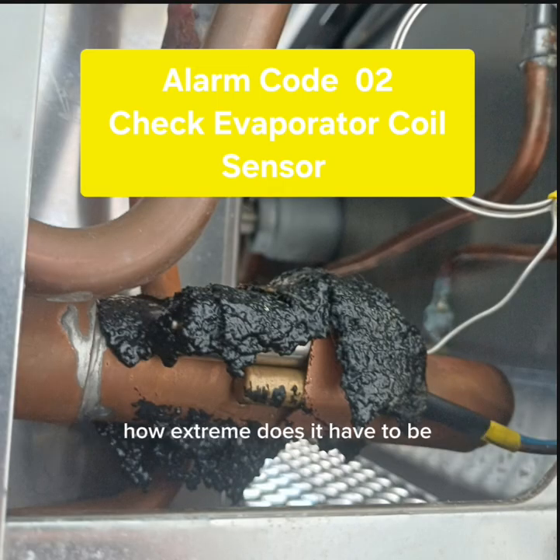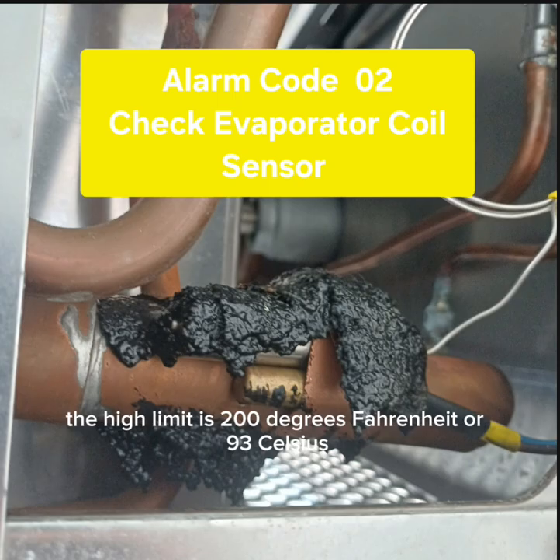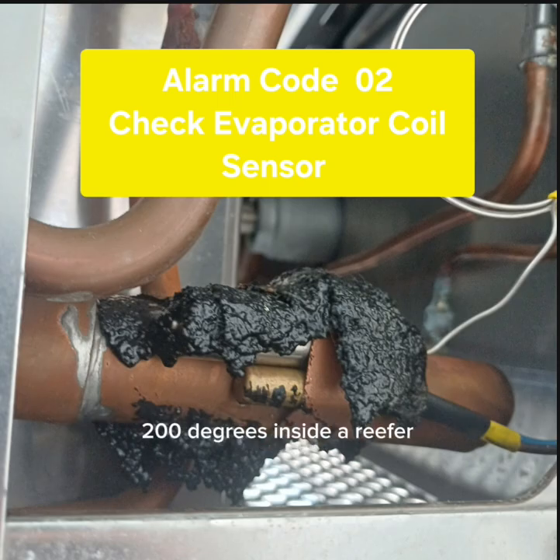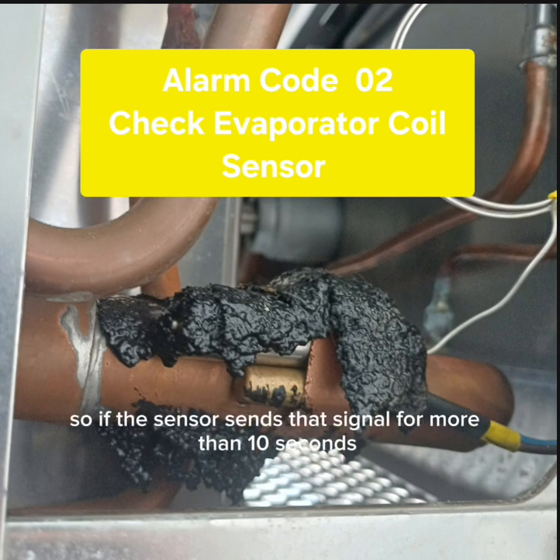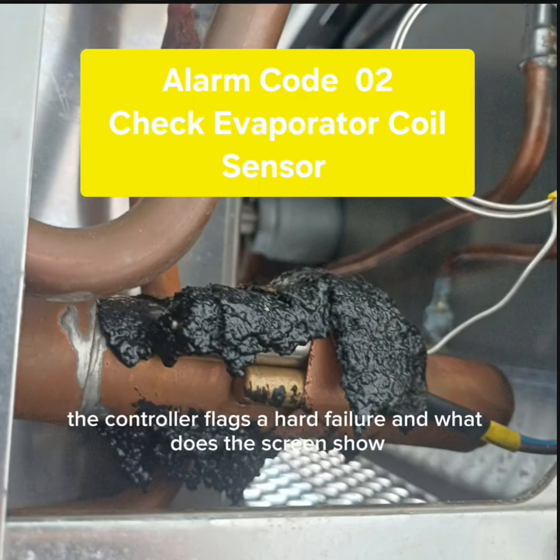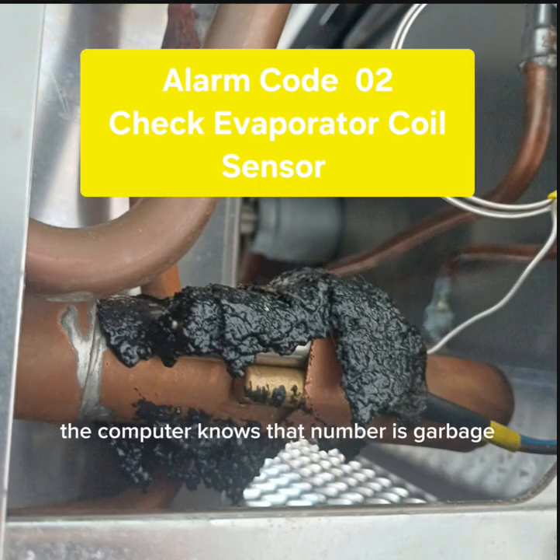What are the limits? How extreme does it have to be? There's a high limit and a low limit. The high limit is 200 degrees Fahrenheit or 93 Celsius. 200 degrees? Inside a reefer? That's oven temperature. Exactly. Unless the trailer is literally on fire, the evap coil is never 200 degrees. So if the sensor sends that signal for more than 10 seconds, the controller flags a hard failure. And what does the screen show? Does it say 200F? Nope, the computer knows that number is garbage.